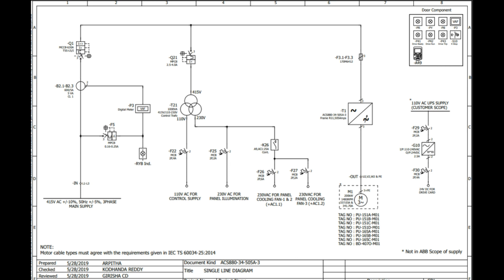Going further on the right hand side you can see fuses F1 to F3. These are three different fuses, and after the fuses the three phase main supply will go to the drive. Here you can see ACS 880, rating 505 amperes and model number are mentioned, and further it is the output that will go to the motor. For this particular model the motor rating is 200 kilowatt. So that's how it will go.